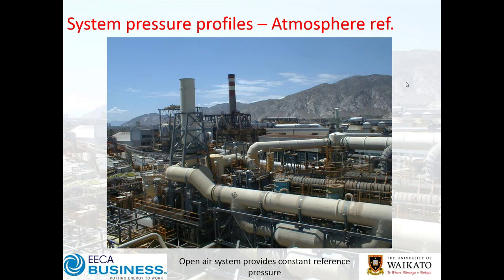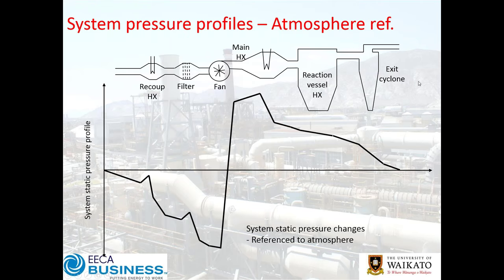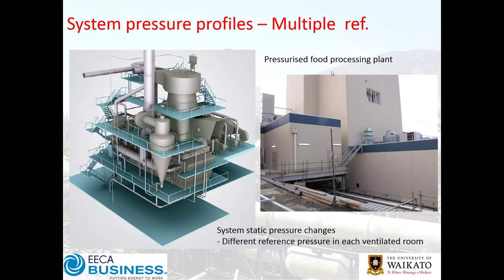The atmospheric reference is worth noting. In a system with a recuperator, filter, fan, heat exchanger, reaction vessel, and cyclone, the static pressure changes at each component, starting and ending at atmospheric pressure — so everything is relative to atmosphere. When the plant is in a building, different parts can be in different segments at different static pressures.